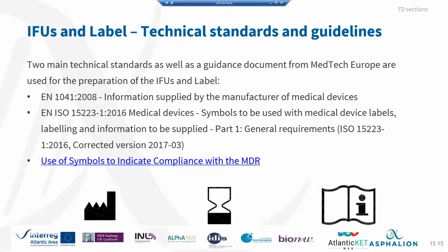Besides these examples, there are two main technical standards which are used to prepare this documentation, the label, and the instructions for use. These are standard 1041 and ISO 15223. These two specifically address which information should be supplied by the manufacturer of medical devices.